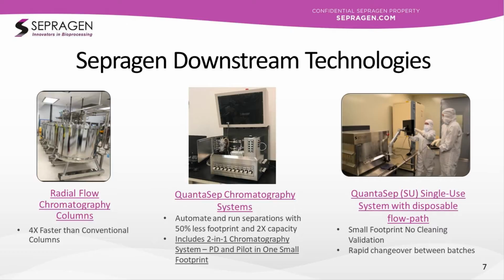This is an installation where they are doing between 10 and 15,000 liters of biologics purification. In this case, it happens to be human plasma, and they're fractionating immunoglobulins. Those stainless steel vessels that you see in the front are not tanks. They actually are radial flow columns, 350 liter size, 4 of them running in parallel, processing huge quantities of biologics, multiples of tens of kilograms of protein per day.